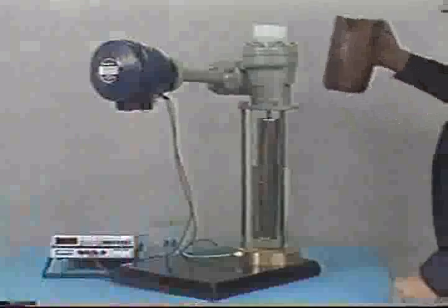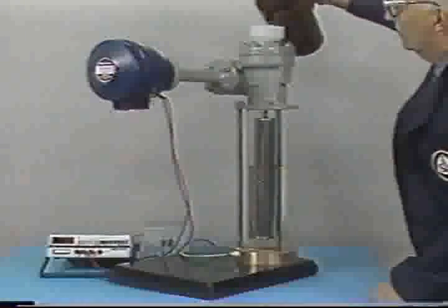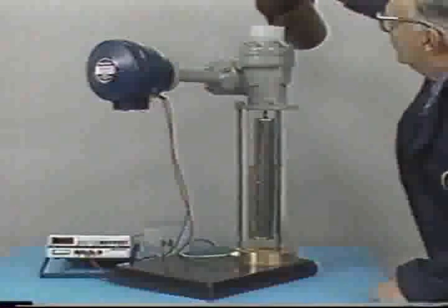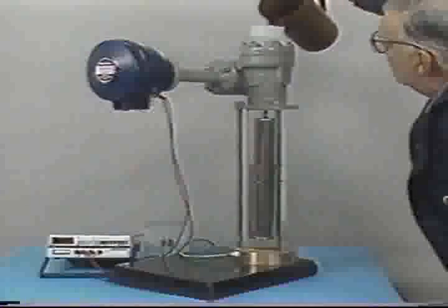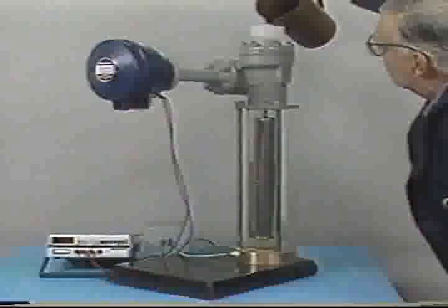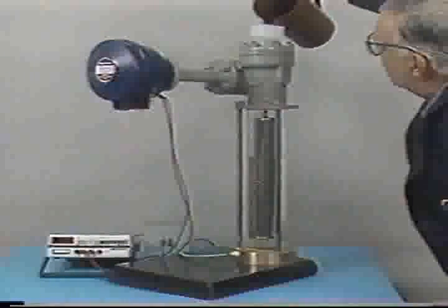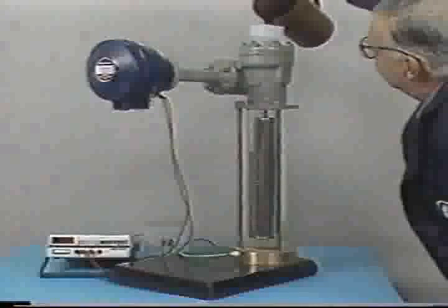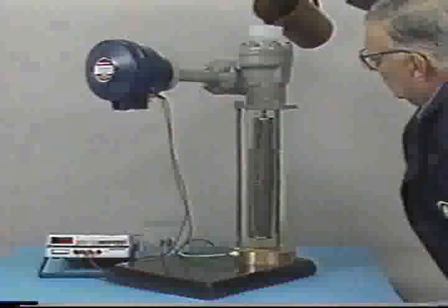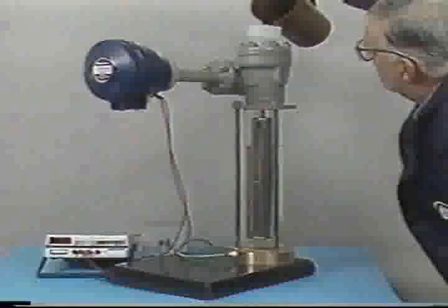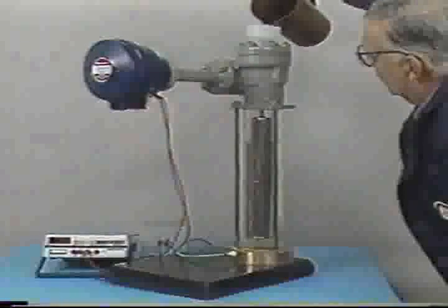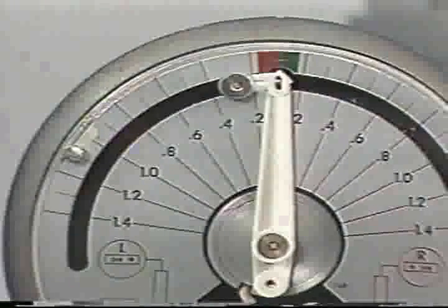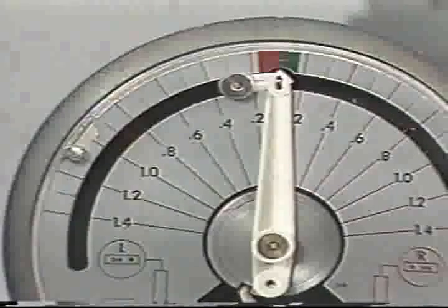the process fluids. By filling the chamber with the lighter phase, you can check and adjust the zero. In this case, the lighter phase is comparable to vapor in a liquid-vapor interface measurement system. Instead of filling to 90%, it's most efficient with this type of transmitter to fill the chamber to 100% to check zero and span. Once the chamber is full, set the specific gravity.